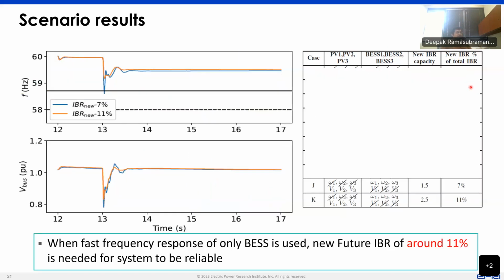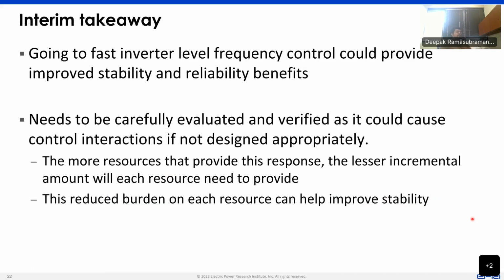But if we actually enable some level of fast frequency response at the inverter level, so maybe we make the battery an enhanced IBR, but we keep the PV as a conventional IBR, then in order to maintain the network response that we want, we can have the future IBR percentage go down as low as 7% or 11%, depending upon the criteria with respect to the transient response that we get. So what this says is that the percentage of some resource that we might need in our future network is going to be heavily dependent on how much capability of the existing network we utilize. And there is a lot of capability that is potentially going underutilized, which we should be able to unlock so that we can leverage this fast response of the network and go to the next level. Now, there is one aspect here that we do need to carefully evaluate, which is how these fast responses are provided, because fast doesn't always necessarily mean stable.